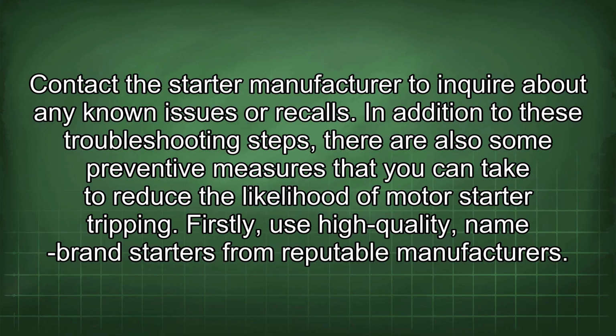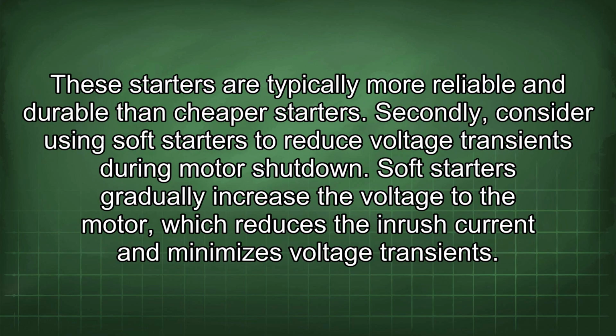In addition to these troubleshooting steps, there are also some preventive measures that you can take to reduce the likelihood of motor starter tripping. Firstly, use high-quality, name-brand starters from reputable manufacturers. These starters are typically more reliable and durable than cheaper starters. Secondly, consider using soft starters to reduce voltage transients during motor shutdown. Soft starters gradually increase the voltage to the motor, which reduces the inrush current and minimizes voltage transients.